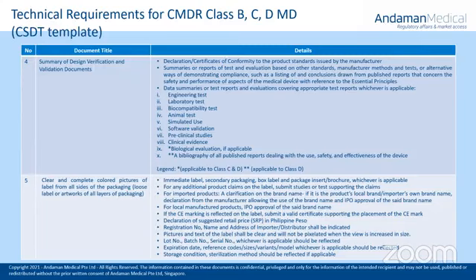Examples of these engineering tests are the electrical safety test reports and EMC, or the electromagnetic compatibility test reports, conforming with IEC 60601. Laboratory tests, biocompatibility tests. So these are for medical devices, especially for invasive medical devices. So you need to have this biocompatibility test as part of your submission dossier, or the biological evaluation that conforms with ISO 10993. So examples of the biocompatibility or biological evaluation tests are cytotoxicity, sensitization, irritation test, toxicity test, and the others.